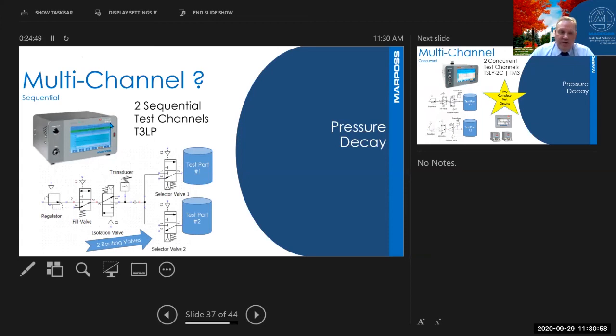So what we're going to do is test part 1 first. When test 1 is complete, then we go on to test 2. But for some people, this is considered multi-channel because it's 2 different parts being tested in the same fixture or something along those lines. And normally these 2 programs are just tested in sequence.